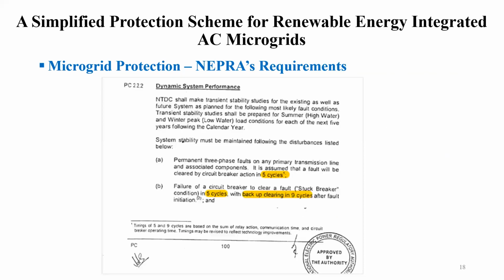Similarly, there is a NEPRA standard requirement that allows 5 cycles for a circuit breaker to operate. It must operate inside 5 cycles, and on failure of the circuit breaker in 5 cycles, backup clearing will happen 9 cycles after the fault. So if a circuit breaker fails, the breaker failure condition is 5 cycles, and it means that it must be backed up in 9 cycles to remove the fault. So these are some of the requirements which we have used in our case study, and we have simulated this.